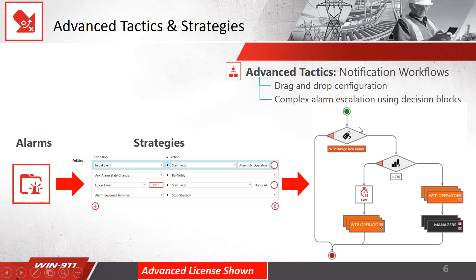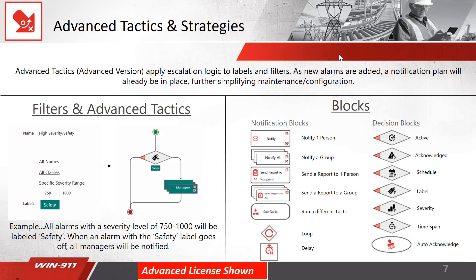In this scenario, if the alarm comes in and is active, we can make a decision: does this alarm have a tag for WTP storage tank? Yes — go this way. No — go this way. If yes, does it have a severity above 750? Yes — call out the WTP operators and the managers. No — wait two minutes and call the operators. So it is a visual flowchart of your escalation path. This slide covers a few more options for advanced tactics and strategies. You have blocks that you can make decisions on — you can notify certain people, groups, do call-outs based on labels, severity, time delays, and acknowledgments. The advantage of using advanced tactics is you can do these state machine type flowcharts, with more options for your escalation paths.